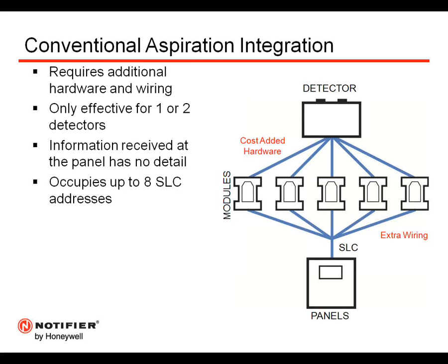Let's compare this to conventional aspiration integration. When we're talking about conventional aspiration integration, it required additional hardware and wiring. We would really consider this only effective for maybe one up to two detectors, and the information received at the panel really had no detail. You were strictly just using monitor modules to monitor dry contacts from the aspiration detector. So the amount of modules that were required would really be determined by the amount of contacts that were provided by the conventional aspiration detector, as well as what the concerned stakeholders were concerned about monitoring from a conventional aspiration detector. And some of them could occupy up to 8 SLC addresses. It also required that cost-added hardware, the extra wiring, configuration, and potentially troubleshooting either during the installation or follow-up service calls.